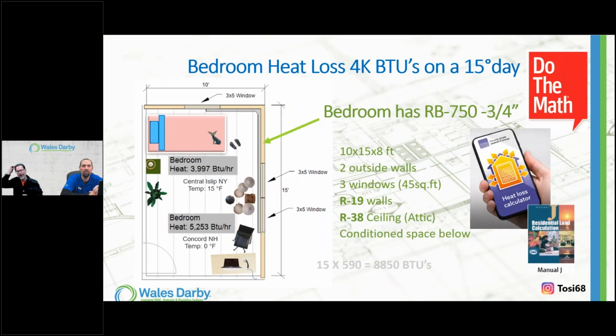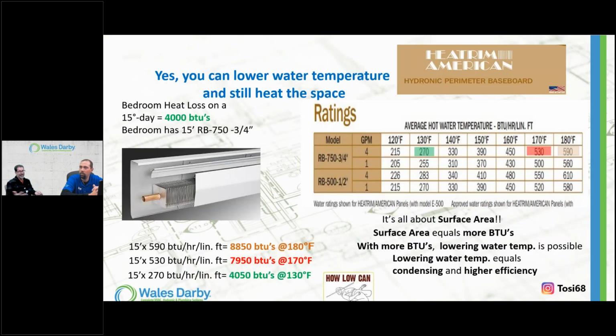So, just please be aware, if you do a room by room, look at the emitters, really determine what the room's requirement is. Again, this room at a 15-degree outdoor temperature only requires 4,000 BTUs. But they have more baseboard in there. It's close to 9,000 BTUs because of using 590 BTUs per lineal foot at 180-degree water. So if I use a chart here, and I realize I'm not getting it done, I'm killing the 1 room out of 10 rooms of this house. Therefore, everything is bigger is better. But I want to go lower water temperature. I want to achieve a greater state of efficiency. Energy dollars in my pocket, not leaving.